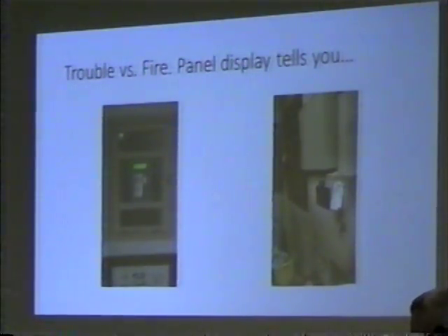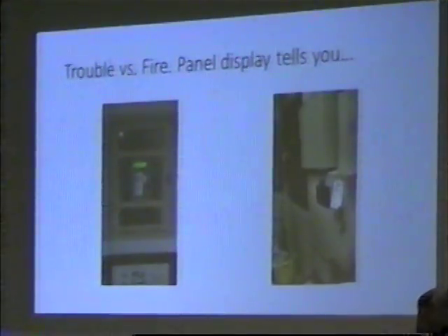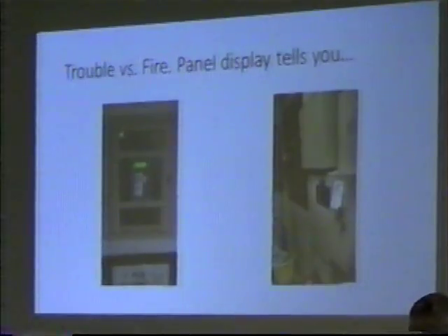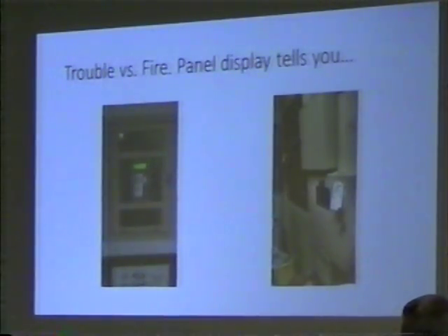A fire alarm means all the bells and whistles are going off. It's showing a fire alarm. A trouble alarm is when there's something wrong with the electrical components in the panel box for the fire system. Whether there's a smoke head that went bad, a battery that went bad, a wire, a pull station, something like that, it's saying, hey, I see trouble in the system, somebody needs to check it out. Well, it's going to tell you on the annunciator whether it's trouble or fire. So make sure you look plainly and see if it's a fire alarm or a trouble alarm before you get on the radio and say what it is, okay?